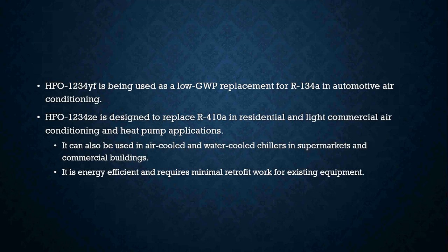Your HFO 1234YF is being used as a low GWP replacement for 134A in automotive air conditioning. The 1234ZE is designated to replace R410A in residential and light commercial air conditioning and heat pump applications. It can also be used in air-cooled and water-cooled chillers in supermarkets and commercial buildings. It is energy efficient and requires minimum retrofit work for existing equipment.